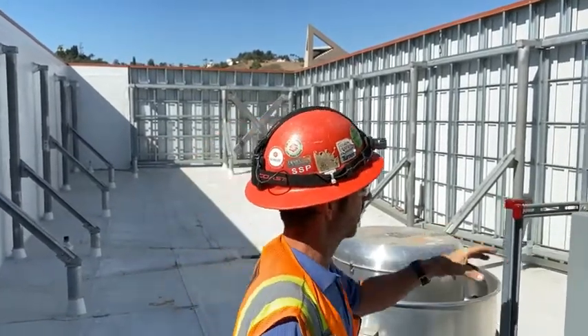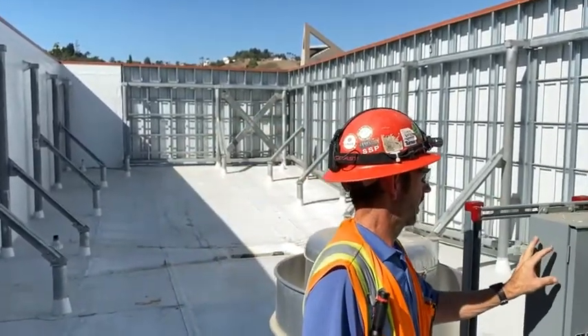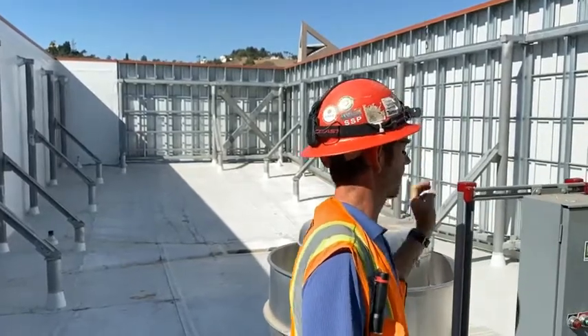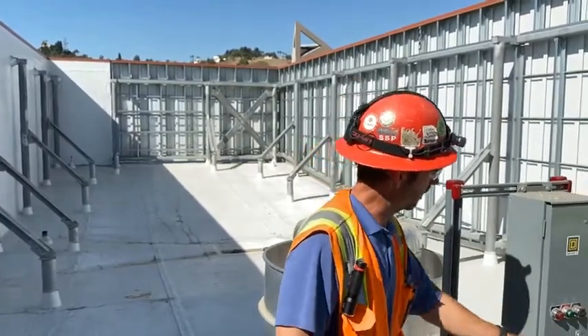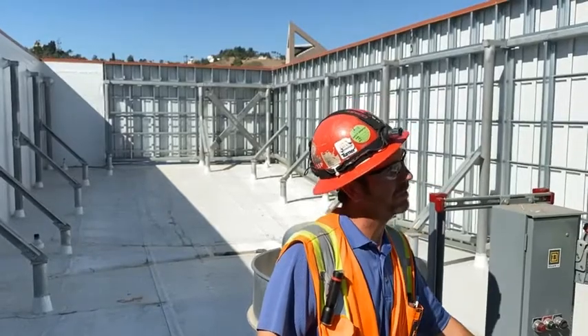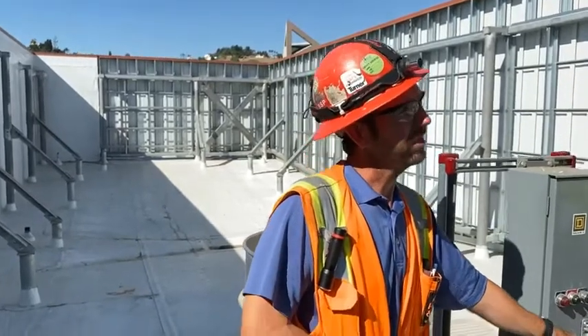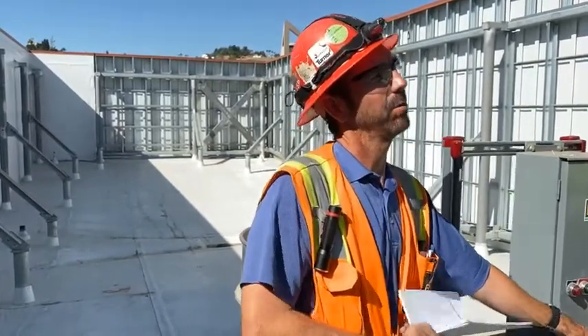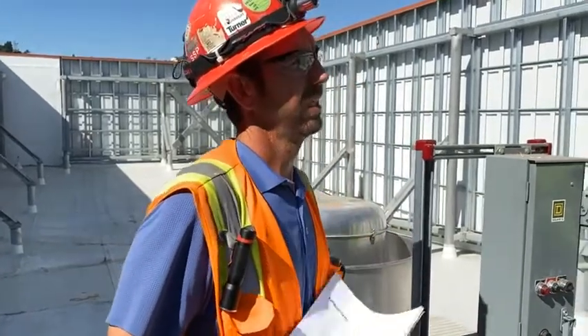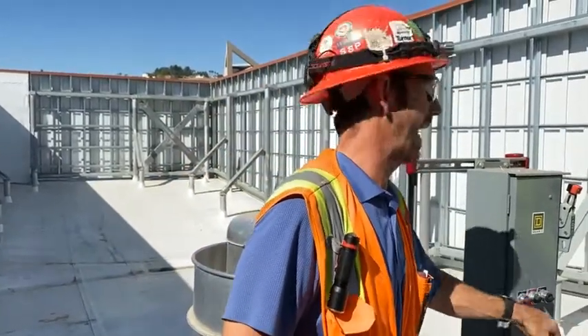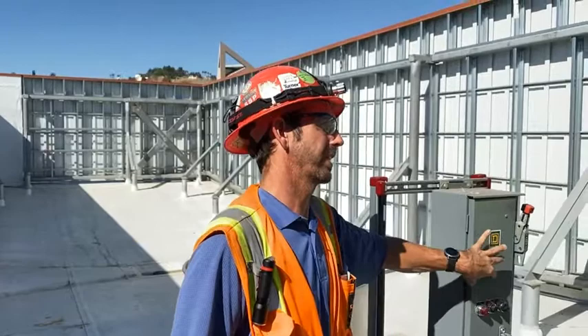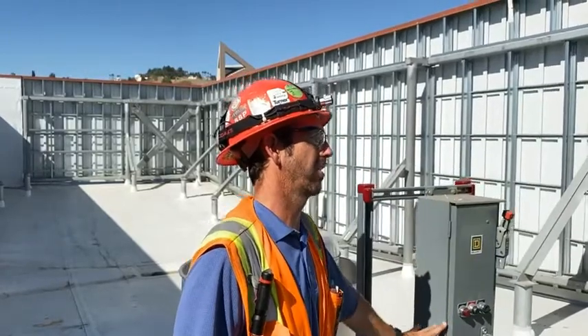So if there's an issue in this fan, if the fan won't turn on, we need to do troubleshooting inside the unit. If you're getting 480 volts on the output of the contactor and the fan's not running, it would be a service call to the mechanical. If you're not getting the 480 coming out of the unit, it'll be a service call to the electricians. Okay, it's their starting device.